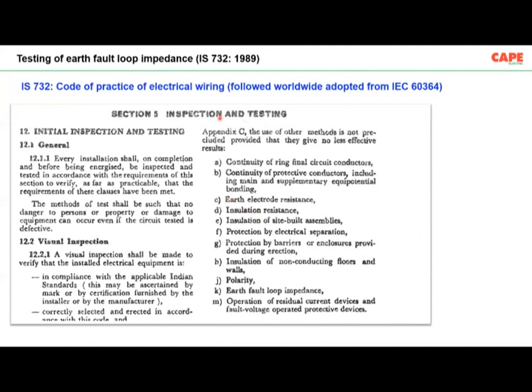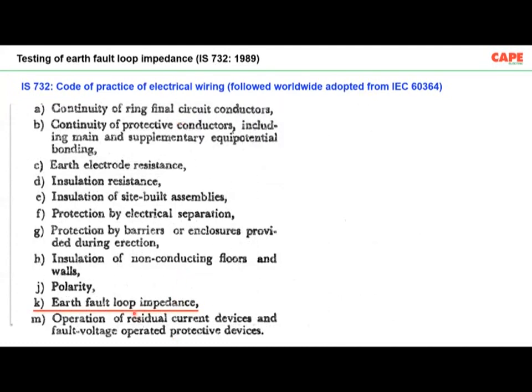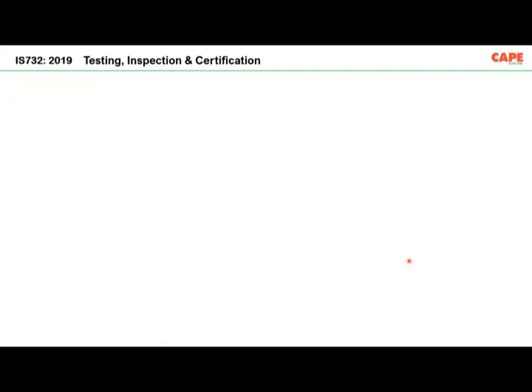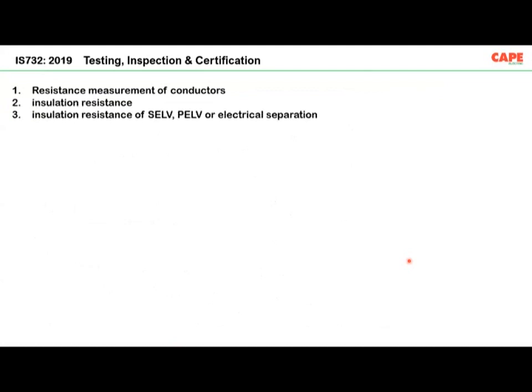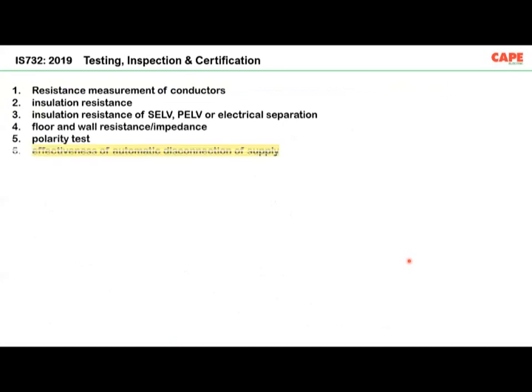You see here, section 5 of this standard talks about earth fault loop impedance testing. This is about testing earth fault loop impedance. So this parameter has been included in the standard approximately 30 years back. But even today, very, very few installations do this particular testing. Then the second, what are the tests required in a modern installation?